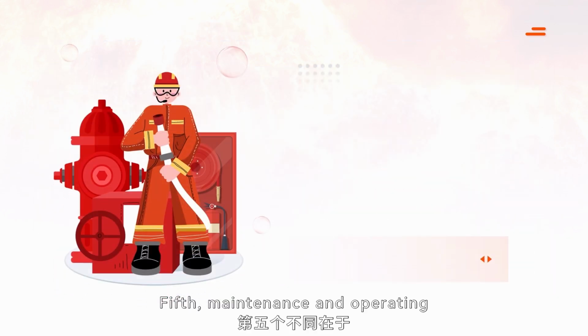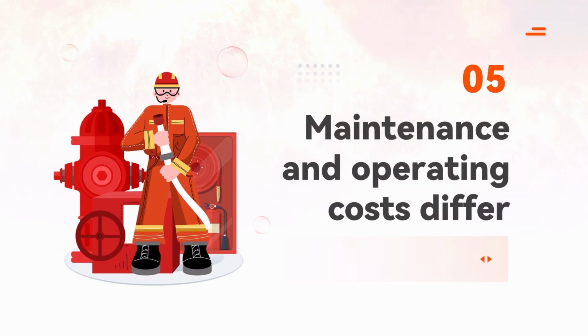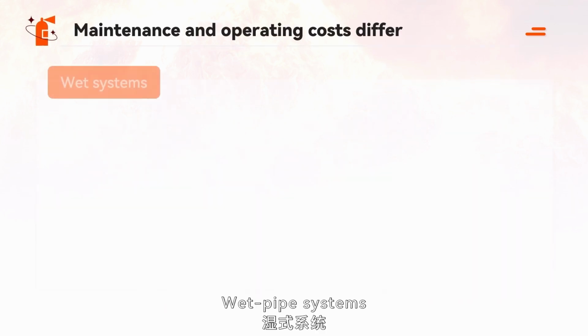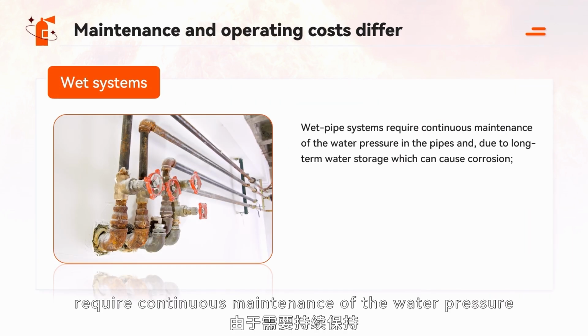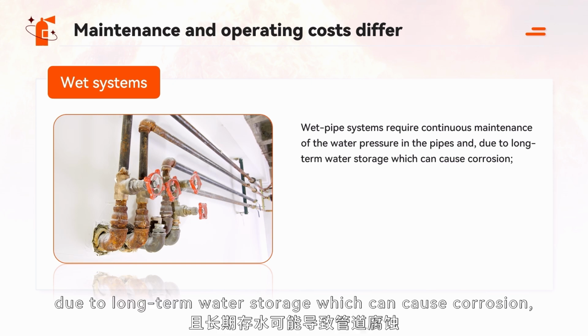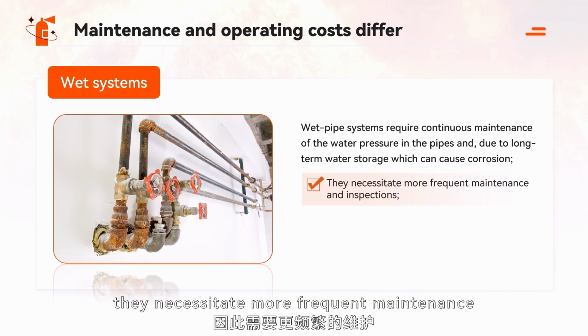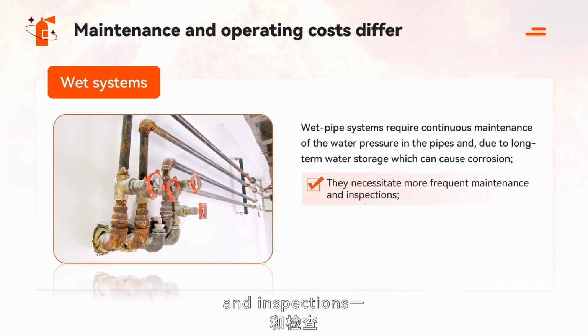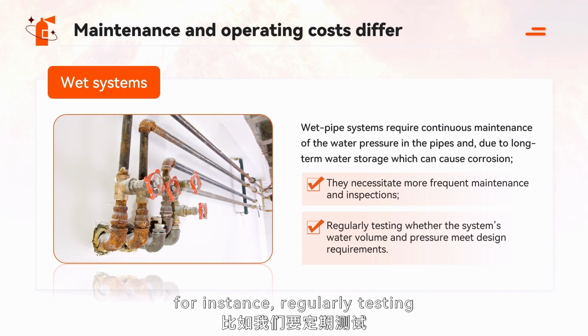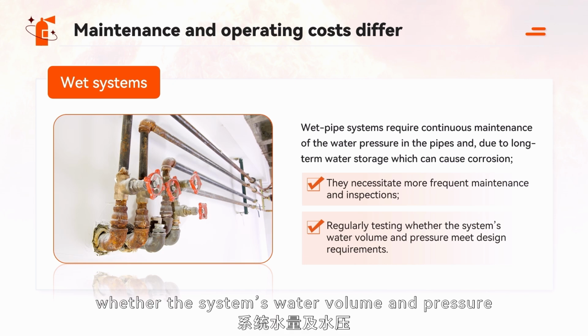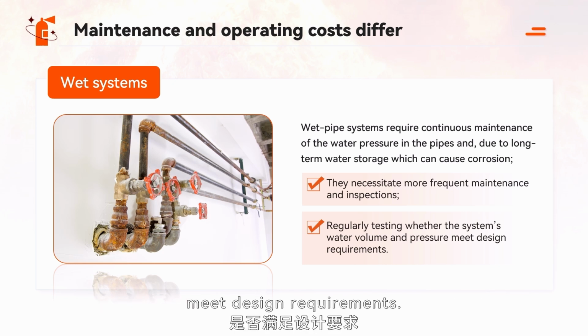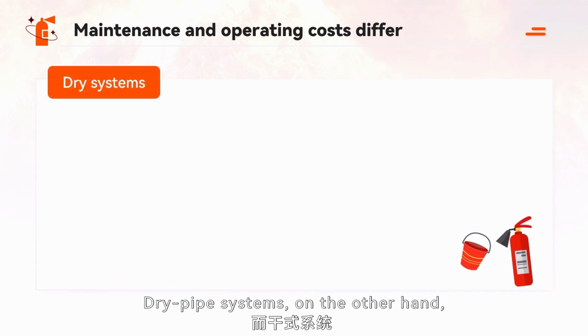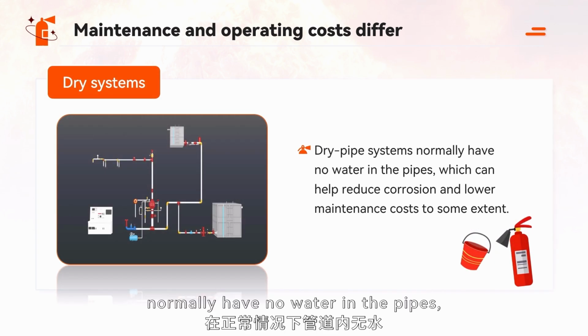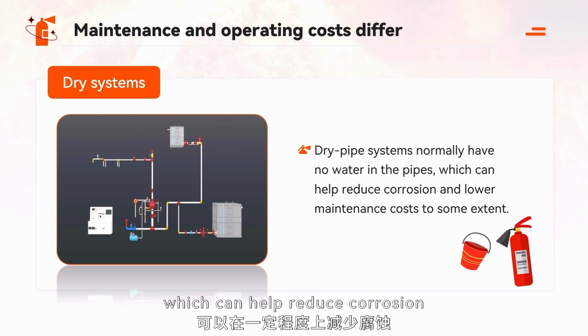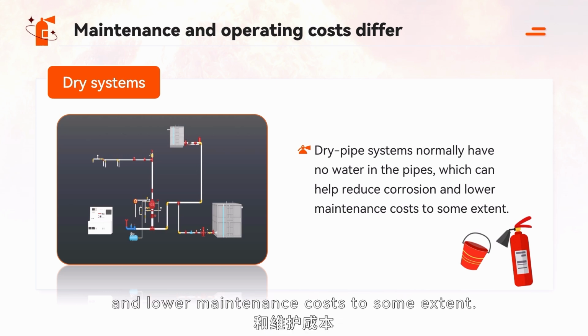Fifth, maintenance and operating costs differ between the two. Wet pipe systems require continuous maintenance of the water pressure in the pipes, and, due to long-term water storage which can cause corrosion, they necessitate more frequent maintenance and inspections. For instance, regularly testing whether the system's water volume and pressure meet design requirements. Dry pipe systems, on the other hand, normally have no water in the pipes, which can help reduce corrosion and lower maintenance costs to some extent.